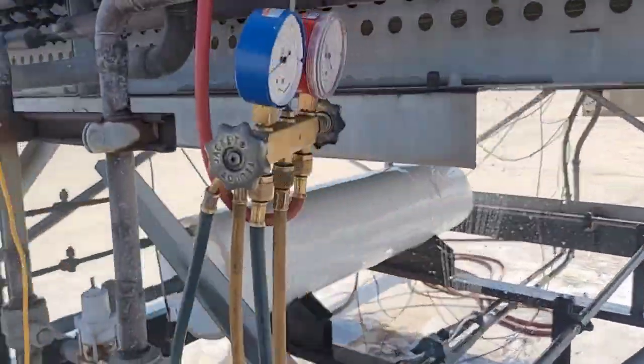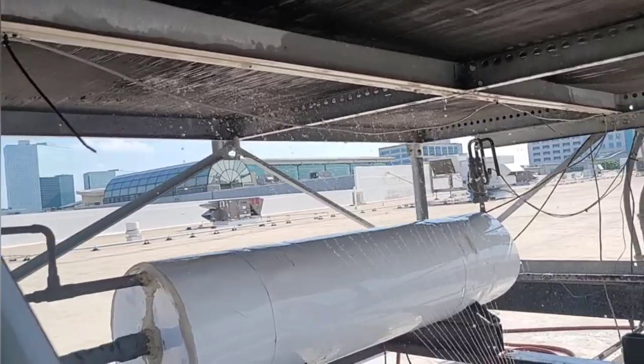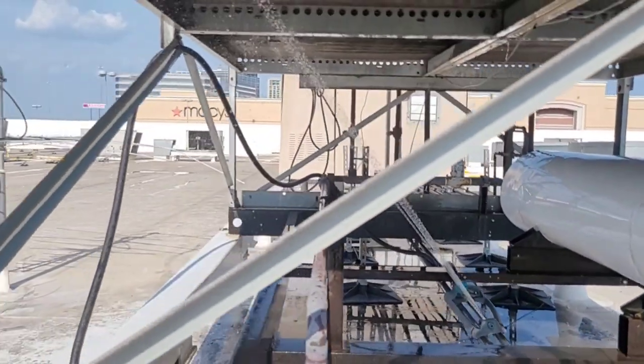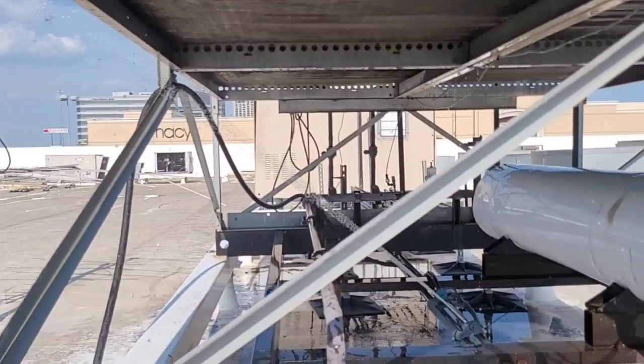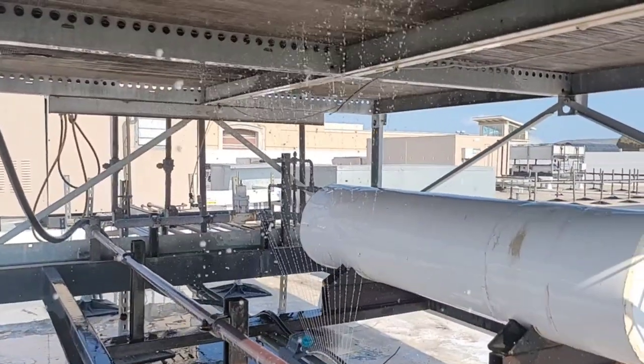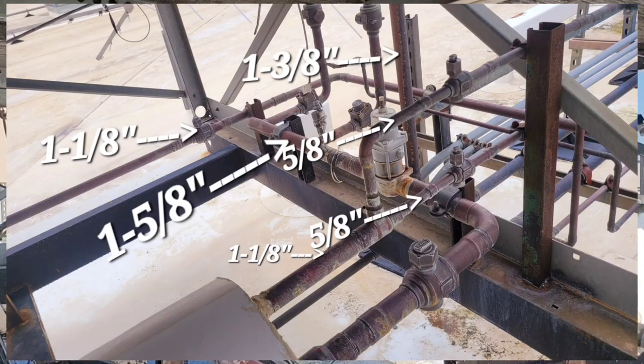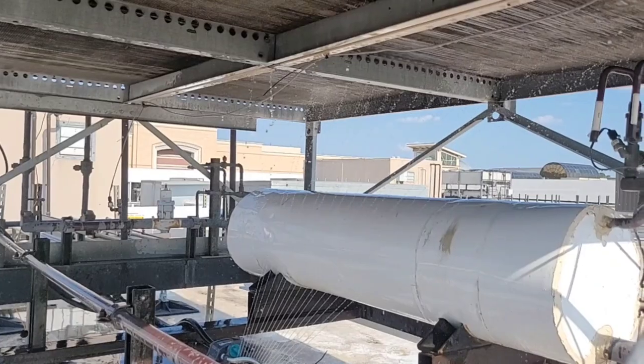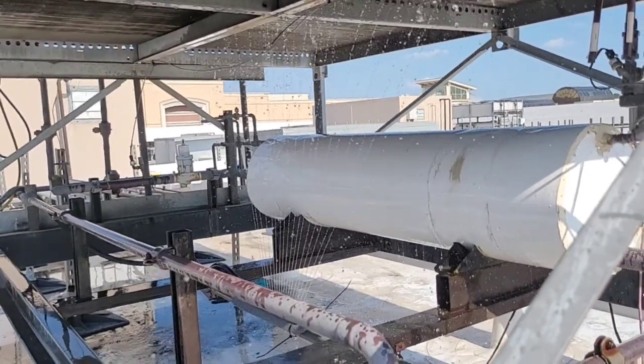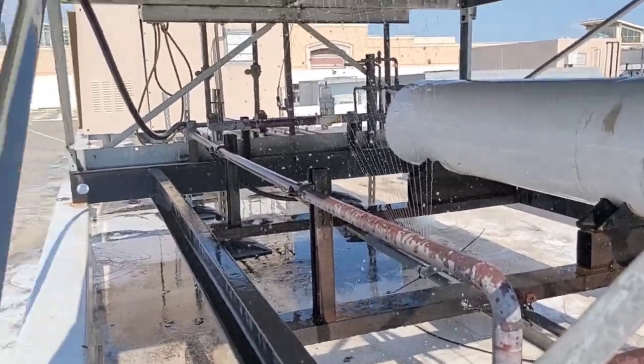After all that, it turns out this condenser just is no good, so I've got a sprinkler on it until it gets replaced — it's time to get replaced. This is how it stayed for about two and a half months. I just went last week and took it off because we submitted a quote to replace the condenser, and it is going to be getting replaced. We're only replacing the top part — not the receiver. We're going to adapt that piping to the new condenser. We've got a crane meeting us there late in the evening and we're going to work all night. We'll use dry ice to keep the product cold. I will try to get some video for you guys on that — not sure how much I'll be able to get since it's going to be dark. See you later.